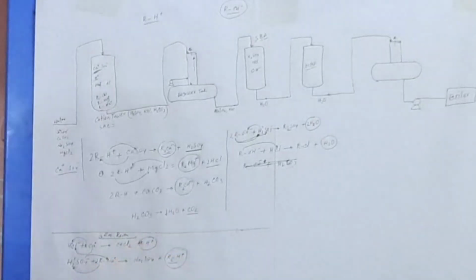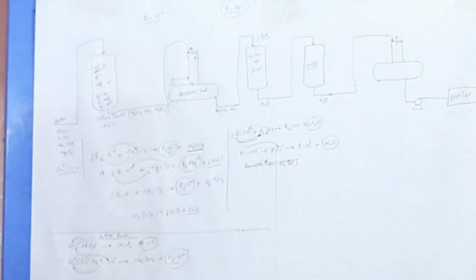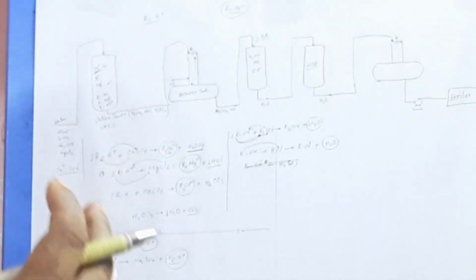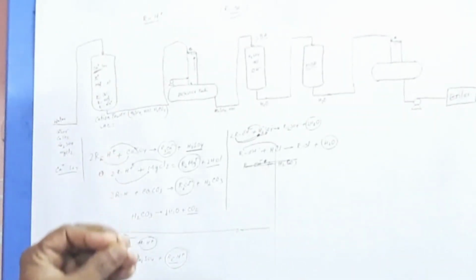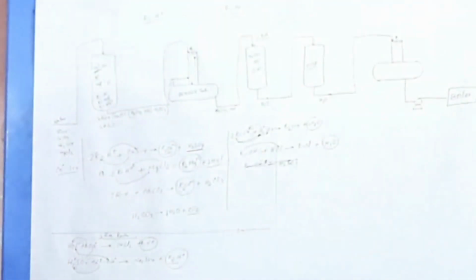The anion tower also absorbs negative ions, or anions. After absorbing anions, this resin also becomes exhausted. So for reactivation, the resin requires regeneration. For regeneration of the anion tower, you have to use sodium hydroxide. By this sodium hydroxide, it is possible to reactivate the anion resin.